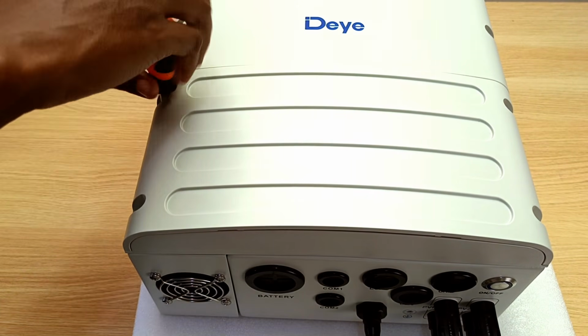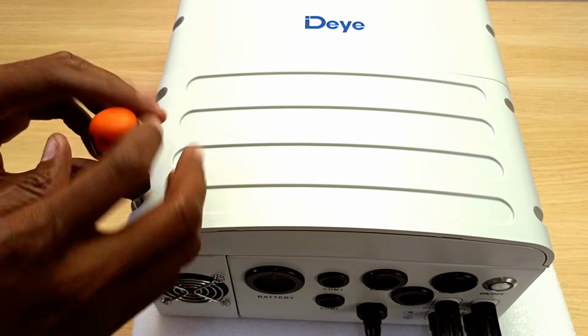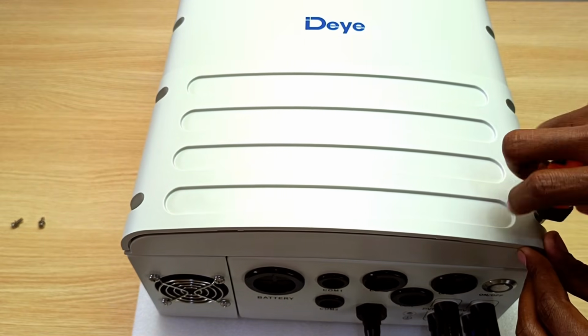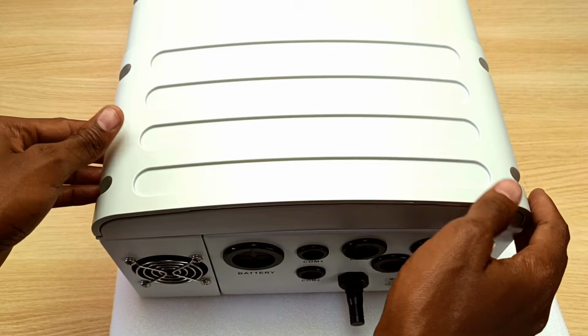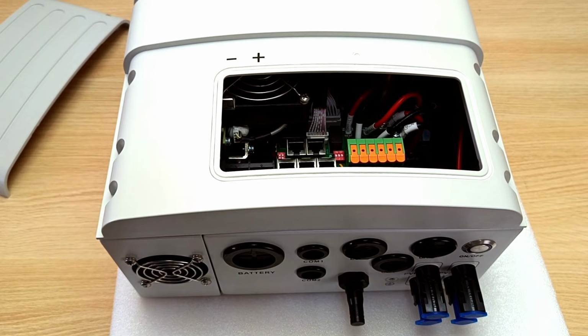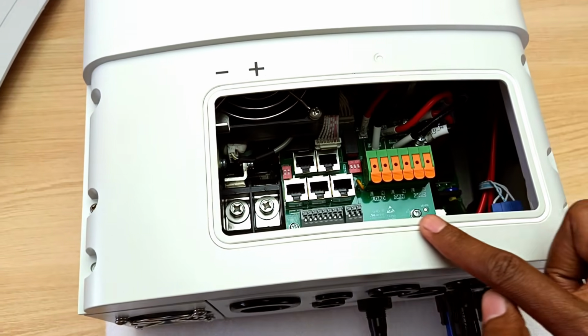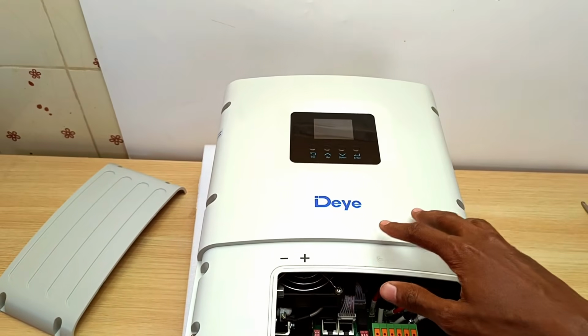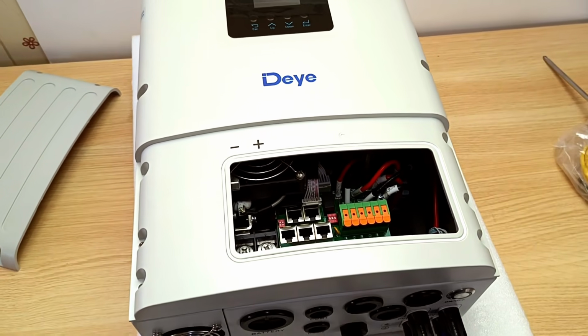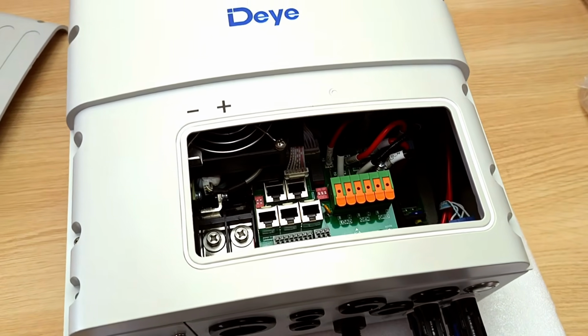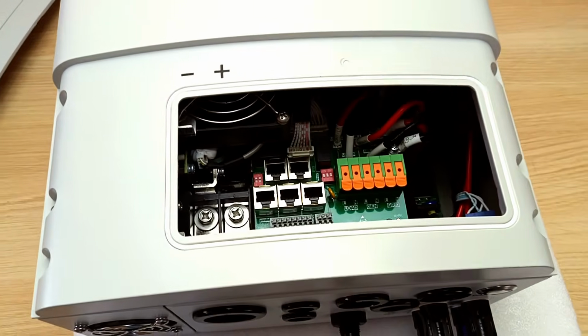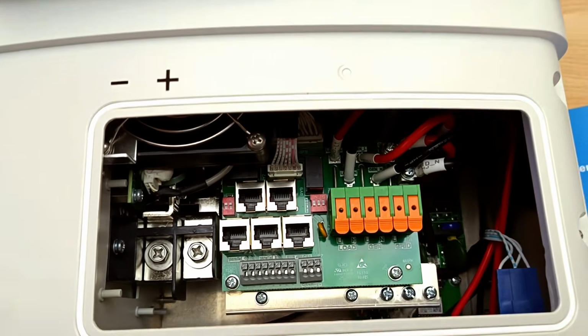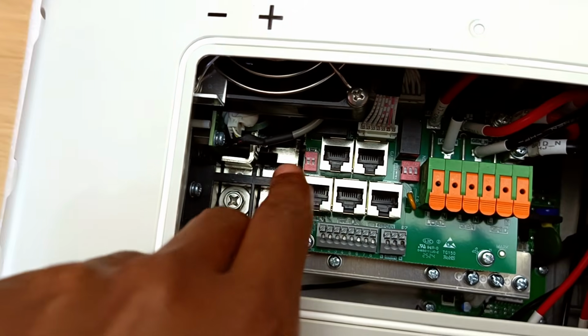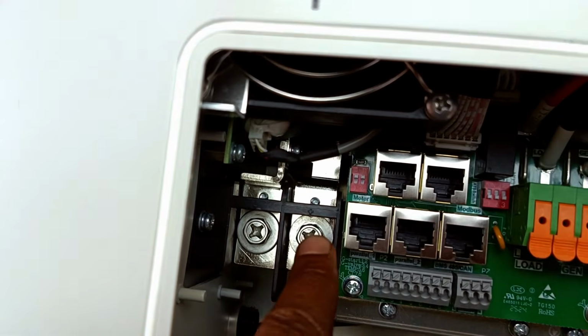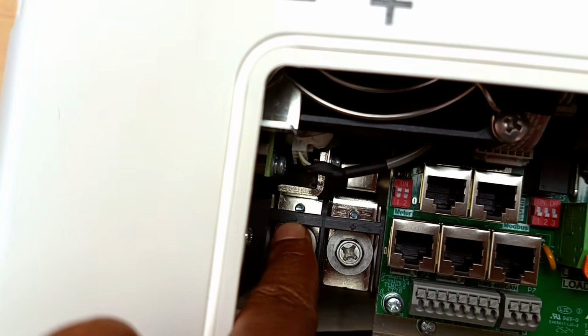All these connections are done by removing this panel. You can see this gasket all around here. This inverter has an IP65 rating. This means that you can actually install it outside. It can keep away the dust, but keep it away from direct sunshine and moisture. This might look overwhelming at first, but it's quite easy. The most important, the battery connections. You can even see the polarity here, positive and negative, also molded into the plastic there, positive and negative.